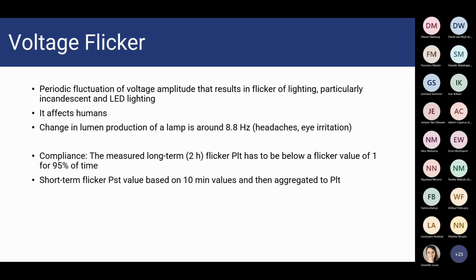Just a note on voltage flicker. This is a phenomenon caused by the input voltage to the equipment, not to be confused with the flicker that could happen on LED driver failure. The impact on humans is the same, but the one we are focusing on here is caused by input voltage to the system. The compliance criteria for voltage flicker is based on the 2-hour flicker, or long-term flicker. That value is compared to a flicker value of 1 for 95% of the time. Your 2-hour value is calculated using 10-minute short-term flickers, aggregated, and needs to be below 1 per unit for 95% of the time. That's the compliance criteria for voltage flicker.